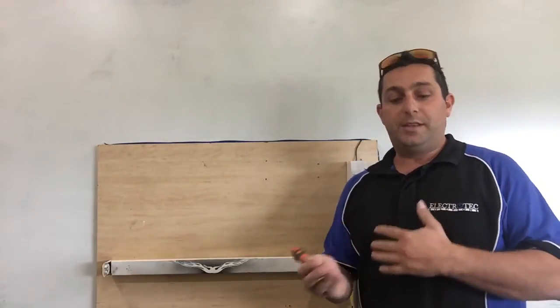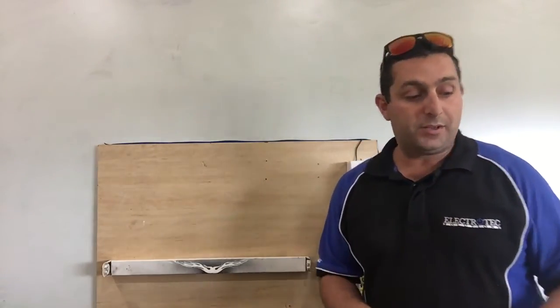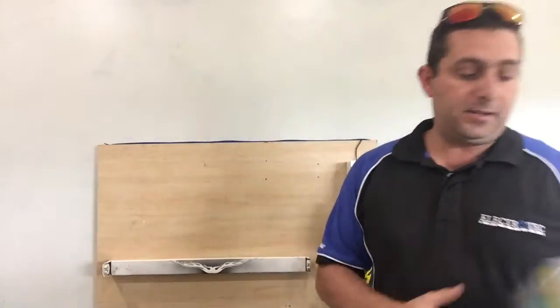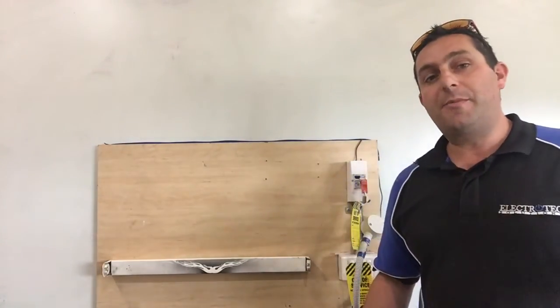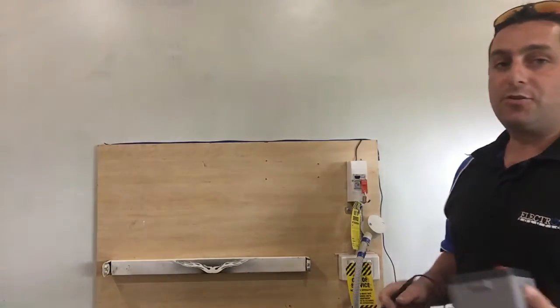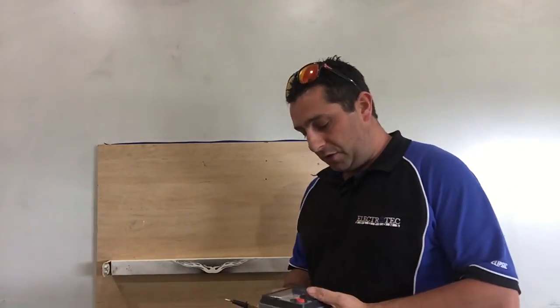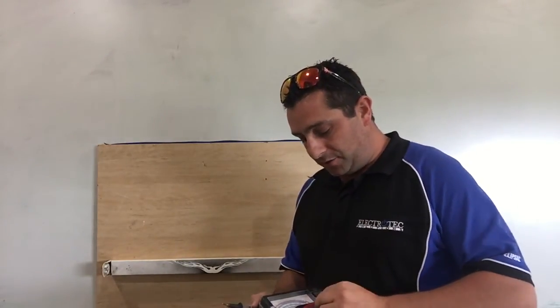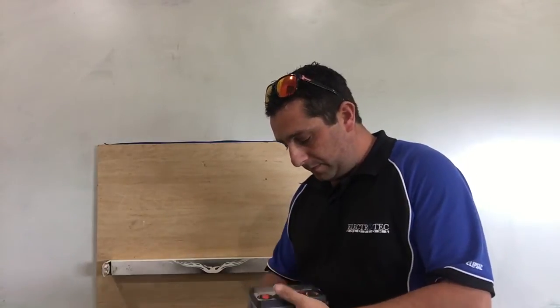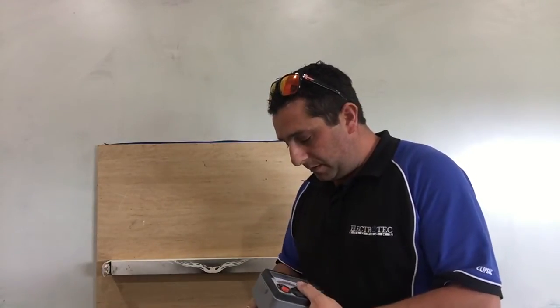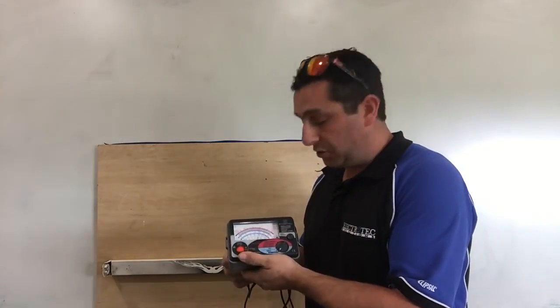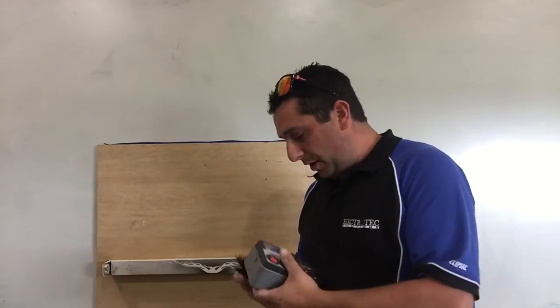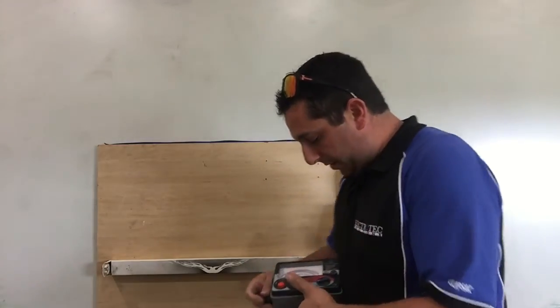We need to make sure that this has been repaired or replaced with the proper equipment, and it's right. And in order to do that, we're going to do a Megger test, or an insulation resistance test. First off, we're going to test the battery in our Megger. Battery showing it's good. And then on the 3 ohm scale, we're going to zero our meter.